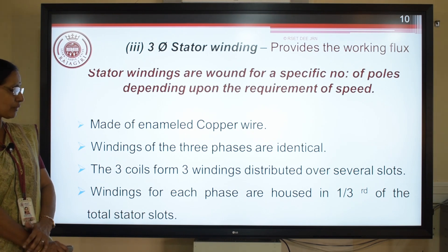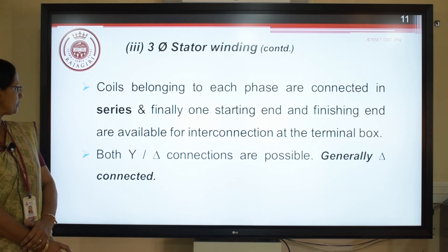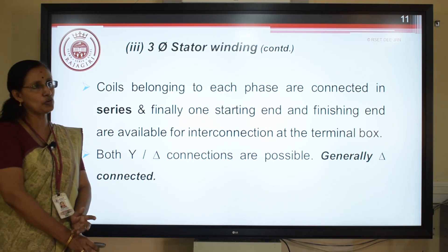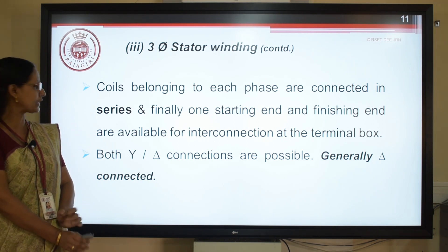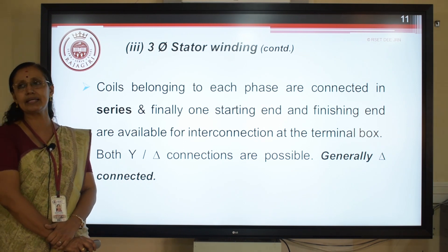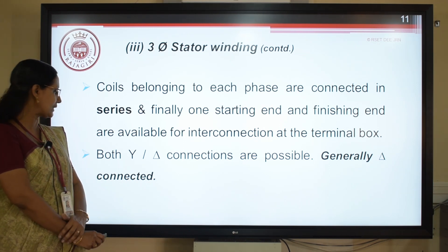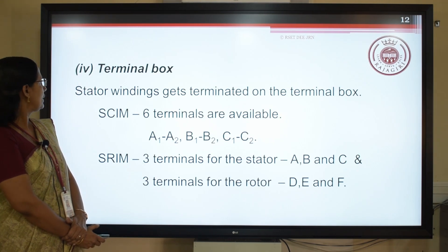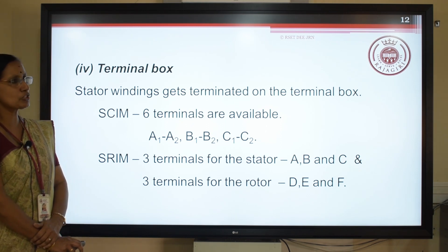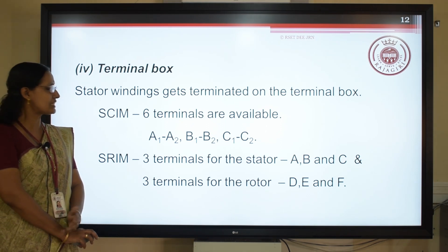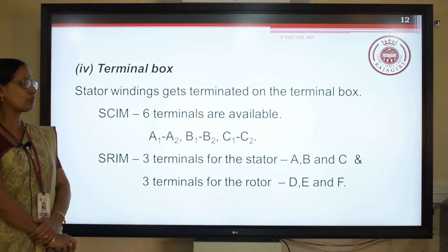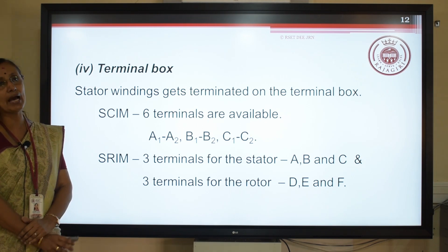The three coils form the three-phase winding distributed in several slots. The coils belonging to each phase are connected in series, giving one starting end and one finishing end for each phase. Being a three-phase machine, the windings can be interconnected either in star or in delta — most probably connected in delta fashion. The stator windings are terminated in the terminal box. For a squirrel cage induction motor, six terminals are available: A1, A2, B1, B2, C1, C2. For a slip ring induction motor, three are for the stator and three for the rotor.